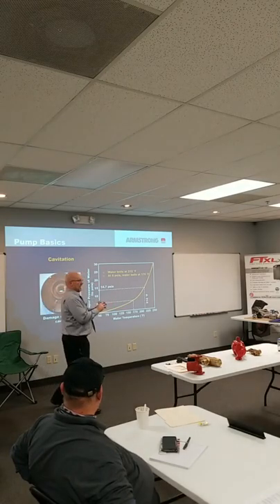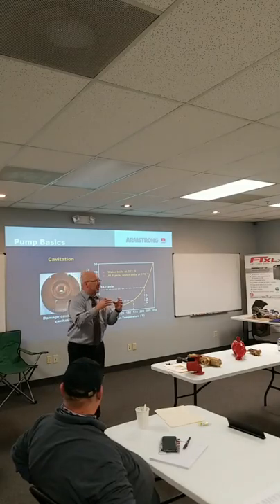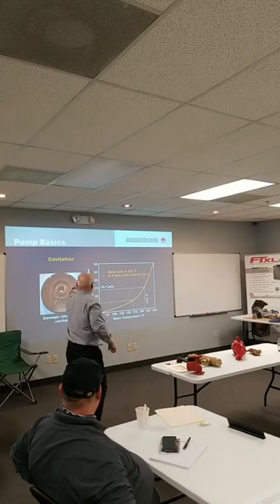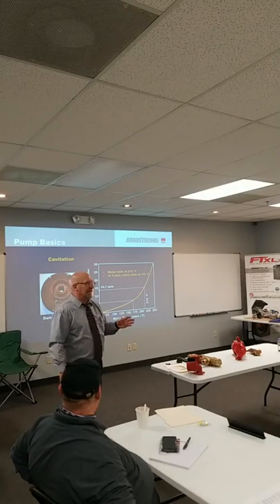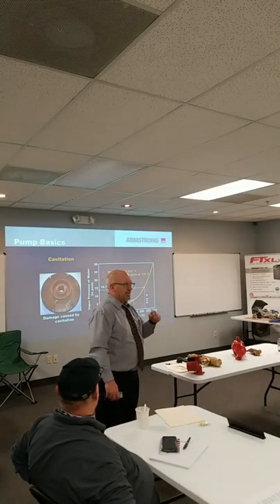It's condensing. It's not the steam that's killing it. It's the condensing. It's going to higher pressure, and it condenses from 1,600 to 1. And it just takes chunks of the impeller. It just takes the brass right out of it. If you've ever heard a pump cavitating, you know. It sounds like you're pumping marbles. It's exactly what it sounds like.